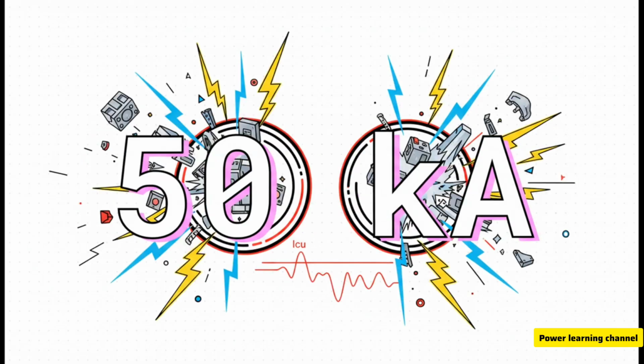Next is ICU, or maximum fault breaking. Imagine our breaker has an ICU of 50 kiloamps. That's 50,000 amps. This is your ultimate safety limit. This is the absolute maximum fault current the breaker can safely interrupt before catastrophic physical failure. I mean, if a fault exceeds this number, the breaker might literally blow apart.